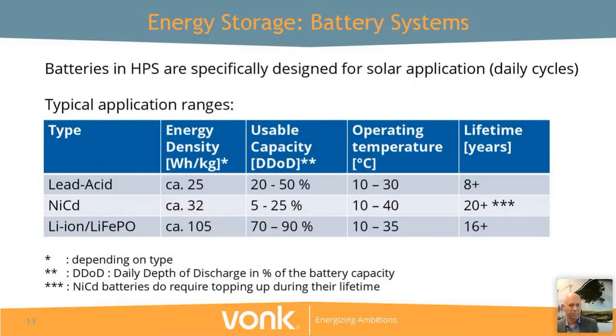For example, in the platform situation, we discharge our lead acid batteries to 50%. You can go lower, but that will drastically reduce the lifetime of your batteries, and you don't want to exchange them too often. Temperature is also important. In hot climates, you'd tend to look at nickel cadmium, for example. But per situation, you really have to look at what kind of battery is available and suitable, and take all the different factors into account.